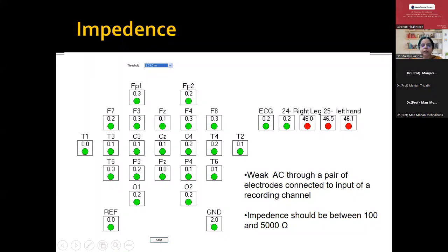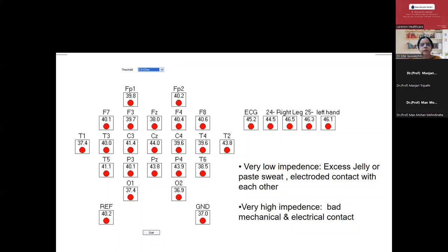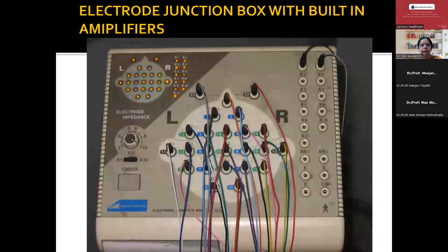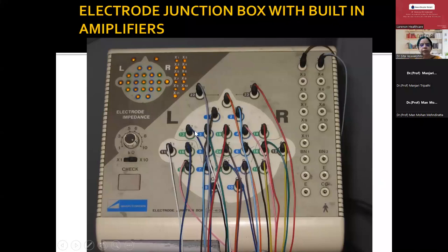Impedance should be between 100 to 5000 ohms. If everything is red, the impedance is not within that range. Low impedance occurs when you apply too much gel, when there is a lot of sweat, or when two electrodes are in contact with each other — no two electrodes should touch. Very high impedance occurs whenever there is bad mechanical or electrical contact. Nowadays we have an amplifier with a built-in head box, where this box contains both the junction box for all electrodes as well as the amplifier.